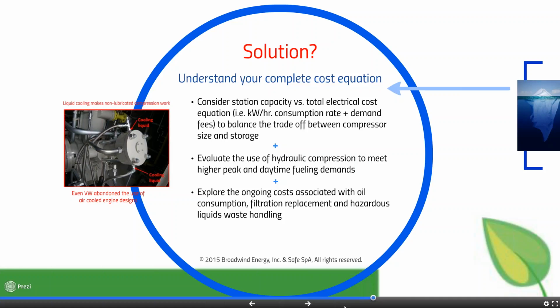I would also look at the remote monitoring capabilities of your compressor as a way to help you with diagnostics. If you can monitor and measure the outputs of the gas temperatures and the gas volumes, and keep an eye on the maintenance needs of the compressor, you can keep your maintenance in the scheduled windows. Even if it's not in a scheduled window, if you're tracking it, you can manage a repair rather than having to deal with it as an emergency call out. That kind of trending data is critical. So I would look at a compressor that is featured in such a way that it can measure vibration and trend that, and that it can measure temperatures and pressures and trend that.